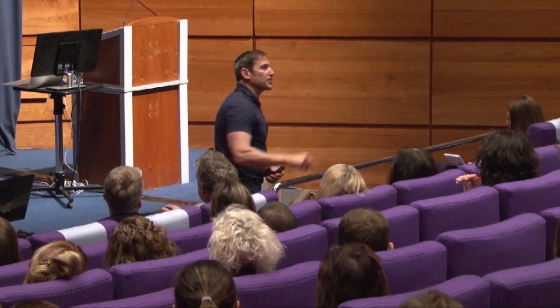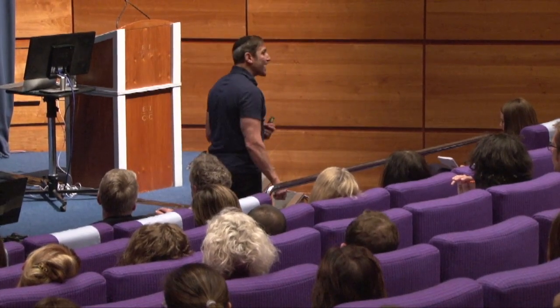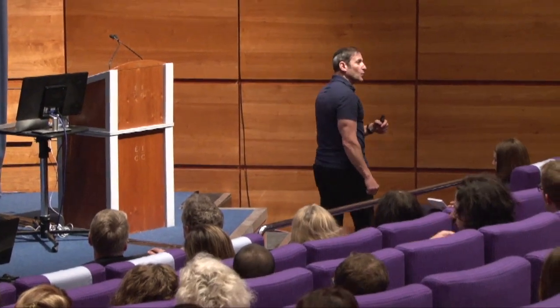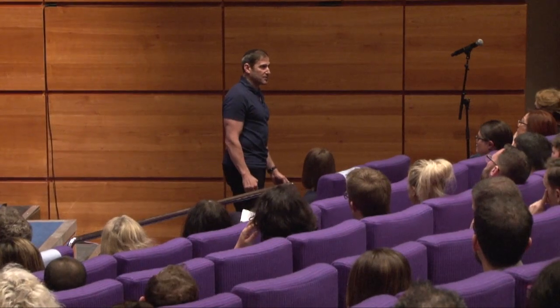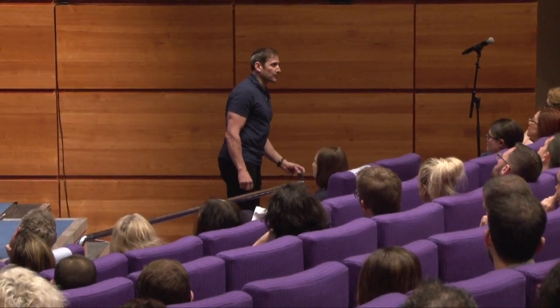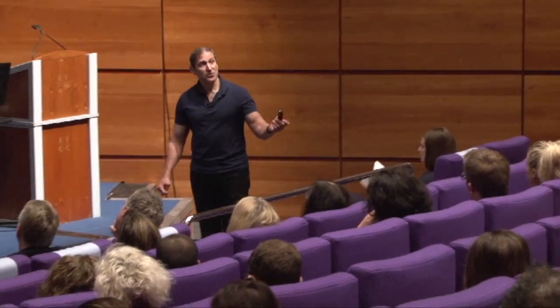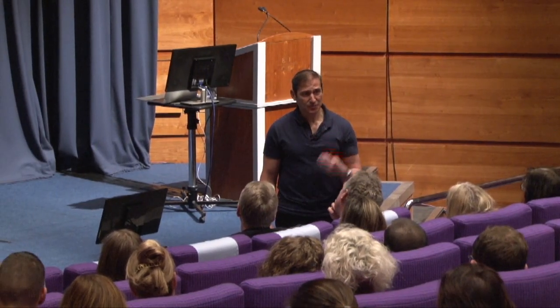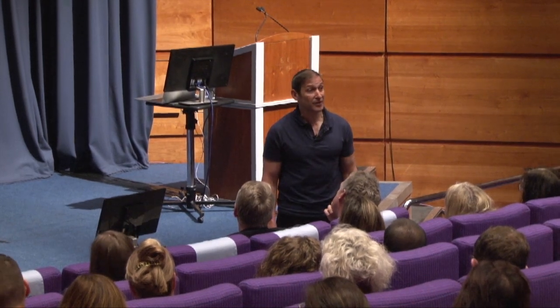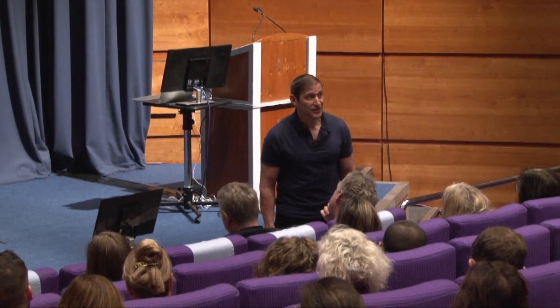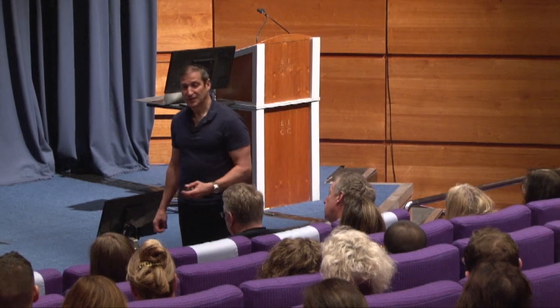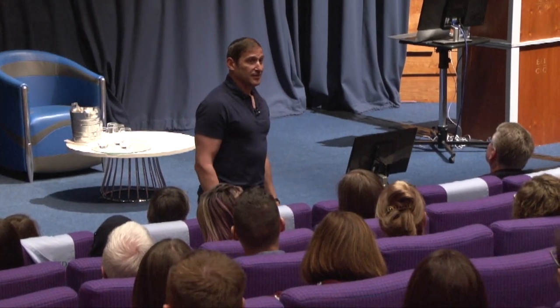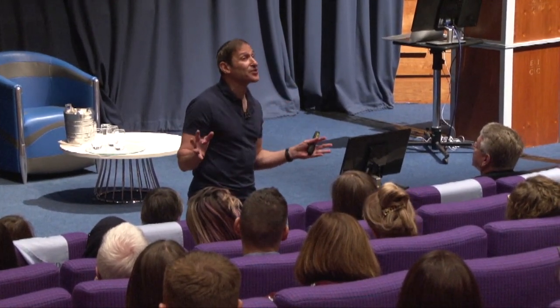So the pacemaker in the center of that scanner is going to act differently than that same pacemaker when you're doing the lumbar spine. Do you understand that? For those of you with a cardiology background, it will switch to asynchronous mode if you're doing the lumbar spine. And it will go back to auto-pacing and detecting if you didn't take care of it beforehand. In the center, it won't even know you're in a magnet, and it will keep sensing if you didn't program it prospectively. I don't care how many Hall switches are there. It won't detect it.